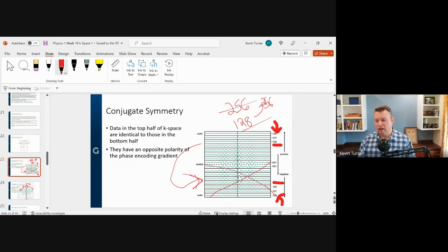So yes, the matrix determines voxel size and pixels. But voxels or pixels per echo, I don't know if that's exactly the right way to say it. The matrix determines not per echo but the total amount. The matrix for the phase encoding determines the total amount of echoes collected, which is pixels in one direction. And the frequency just determines the number of data points taken from the echo, so that's the number of pixels in the frequency direction.